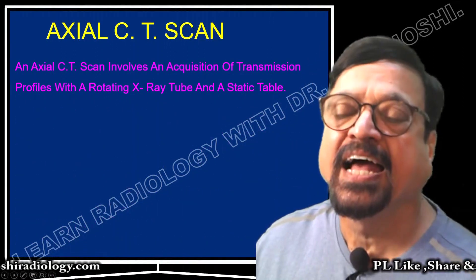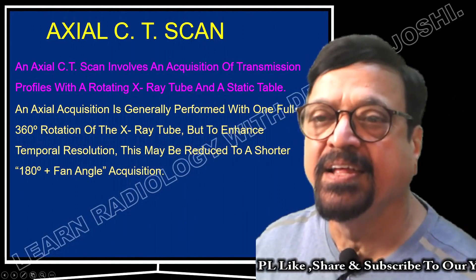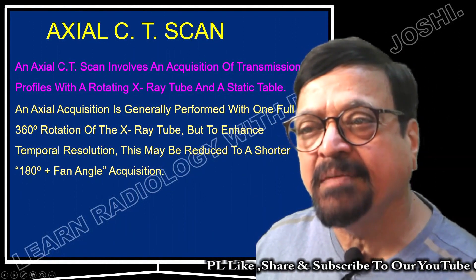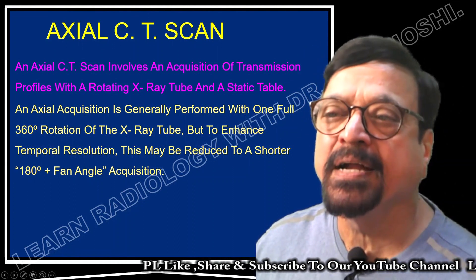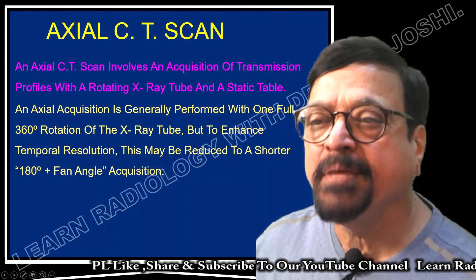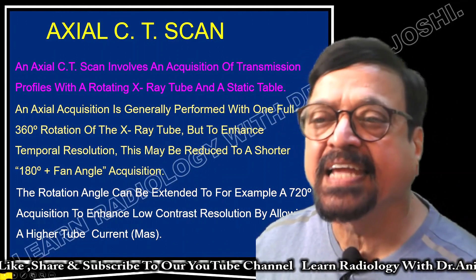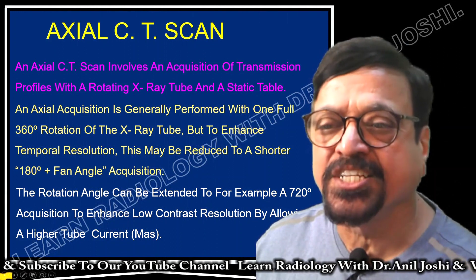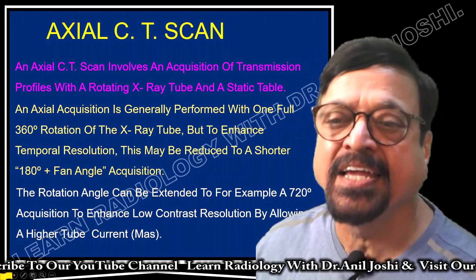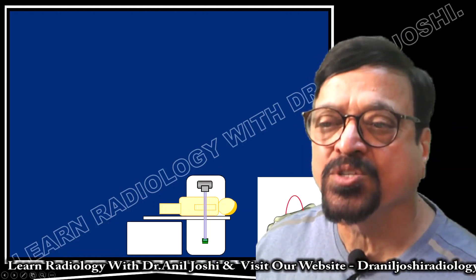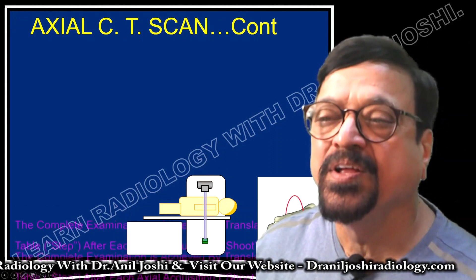Now let's look at the details of axial CT scanning. The axial CT scan was the earlier technique and involves acquisition of transmission profiles with a rotating X-ray tube and a static table. Axial acquisition is generally performed with one full 360-degree rotation of the X-ray tube. With enhanced temporal resolution, this may be reduced to a shorter 180 degree plus fan angle acquisition. The rotational angle can be extended to 720 degrees to enhance low contrast resolution by allowing a higher tube current. The table moves 10 mm per section and stops after each rotation — so it was taking more time, which was a major disadvantage.